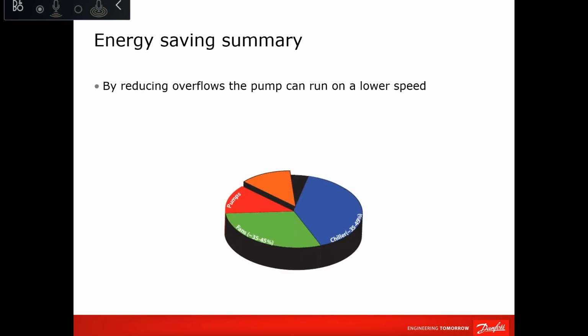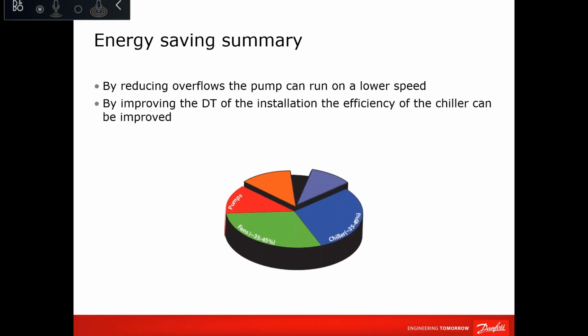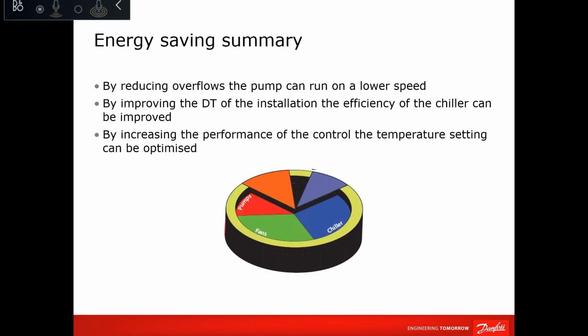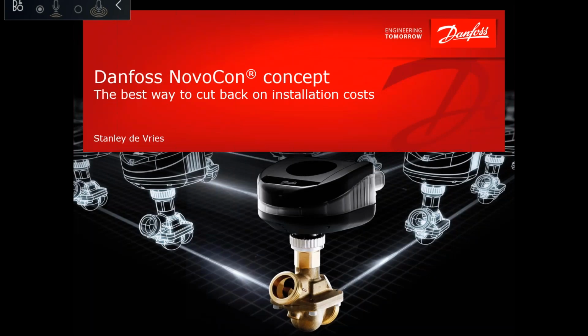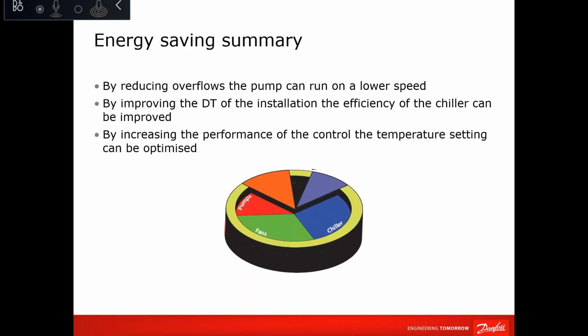So, summary: by reducing the overflows, the pump can run at lower speed. By improving the delta T of the installation, the efficiency of the chiller can be improved. By increasing the performance of the control, the temperature set point can be optimized. Now, this is it from the presentation. We are exactly according to the time.